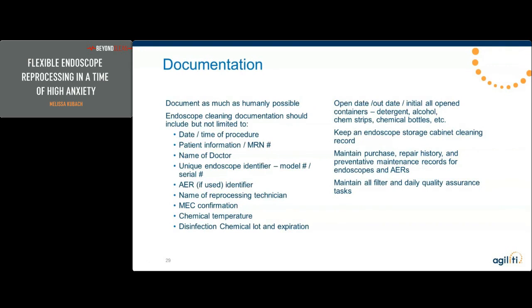But the one thing I want to point out, especially as it pertains to sterilization, I still see a lot of trouble tying the patient to the serial number to the sterilization load. First of all, a lot of times those patient stickers are just not coming down, and it's difficult for someone to go retrieve that when they are probably shorthanded and have more than they can possibly do. They don't have time to chase that down.